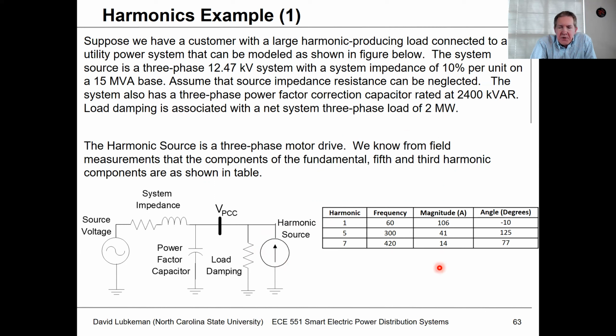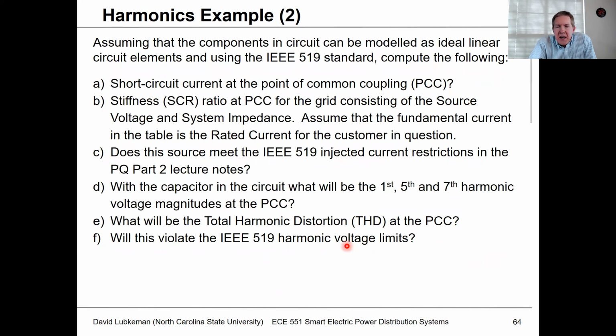And I've got the harmonic source here, which is the same as the harmonic source we looked at before. So what we're looking at is doing different calculations. We want to get the short circuit current at the point of common coupling. We want to get the stiffness ratio, so we know what current levels we need to adhere to. We want to check to see if the currents injected at harmonic levels comply with 519. We want to see what the first, fifth, and seventh voltage magnitudes will be at the capacitor in the circuit. From that, we can get the total harmonic distortion and then see if we violate the IEEE 519 limits.